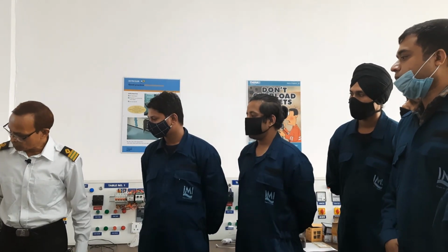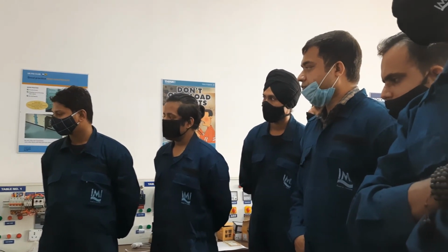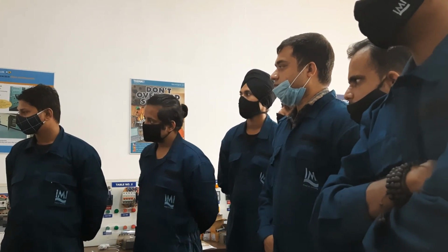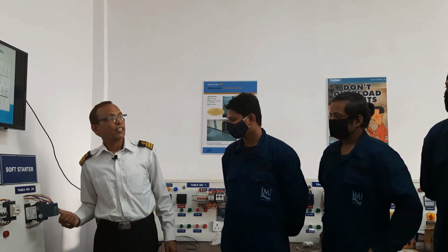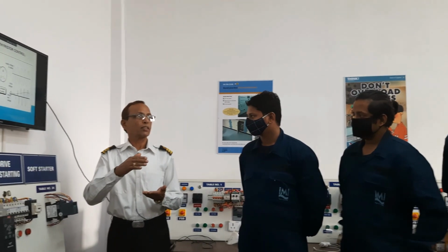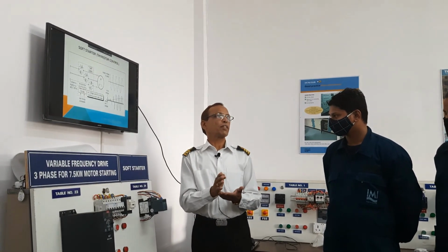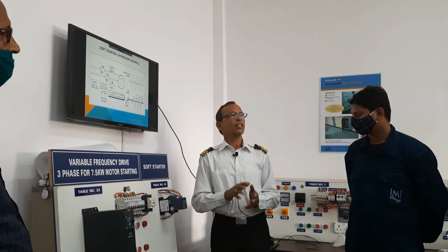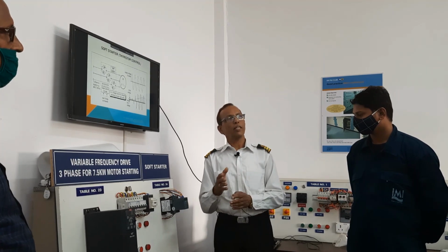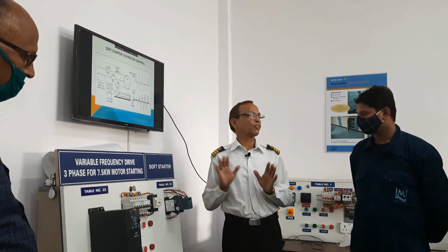But now in this circuit we have directly connected the motor with the soft starter, but we can make it a star delta, where we go star and then into delta. Here we can start with the soft starter, ramping your motor. When the speed comes up, the timer will take place. After this much time, the circuit will change and you can go direct online. Your contact is changed, like star going to delta. That is the basic funda of this.